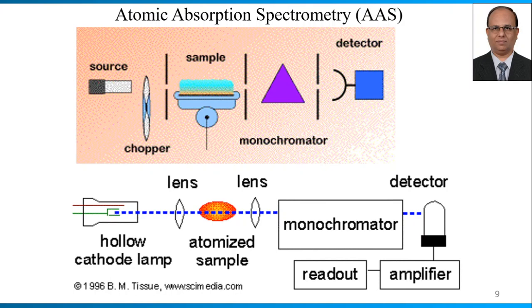The components of the atomic absorption spectrophotometer: the source emits radiations; a mirror chops the radiations into parts — one continuously passes through the flame, one directly reaches the detector. The sample is held in the flame as small atoms after nebulization. These atoms are bombarded with radiations which are absorbed. The transmitted radiations are sent to the monochromators — prisms or grating monochromators — and then to the detector. The source generally uses the hollow cathode lamp, HCL. Either flame, plasma, or non-flame technique is used for preparing the atomic form of the substance, which is then bombarded with these radiations.